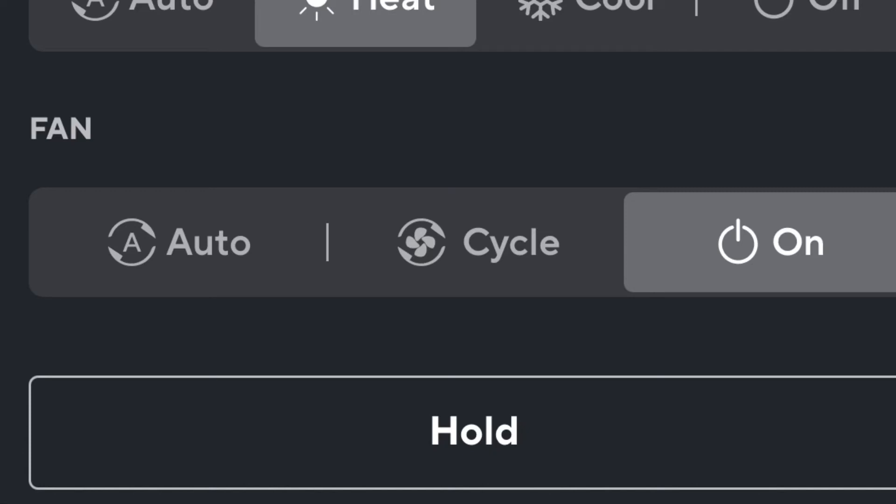Going back to your system — if you find that after hooking up your Wyze thermostat your fan is cycling on and off, how do you temporarily correct that until Wyze can come up with a fix? What they need is an off mode to completely keep that fan off, because your furnace will automatically turn the fan on when the system comes up to temperature and automatically turn it off when the system is done heating or cooling. Those modes in the thermostat do not need to be turned on — and again, this is a Wyze issue.